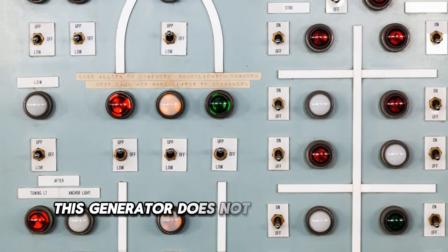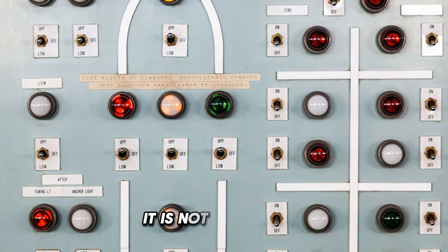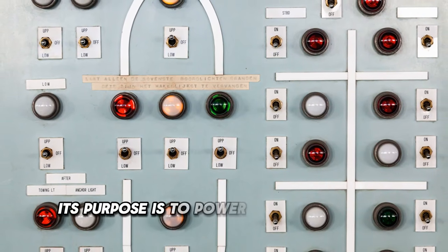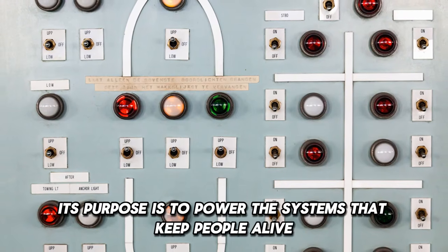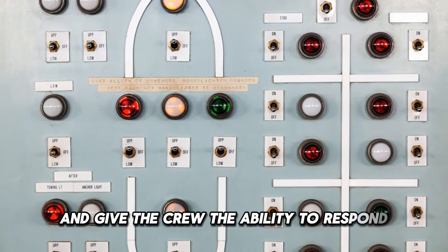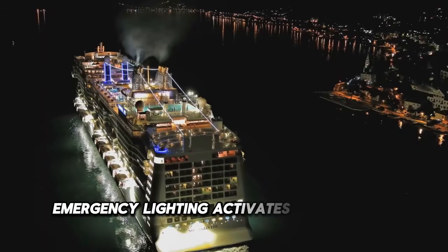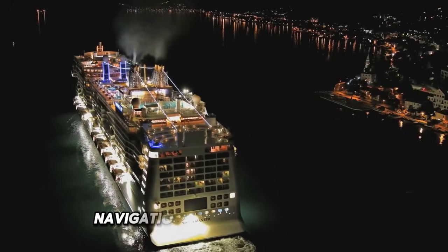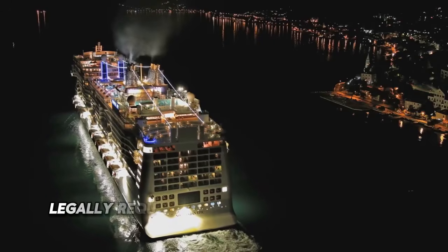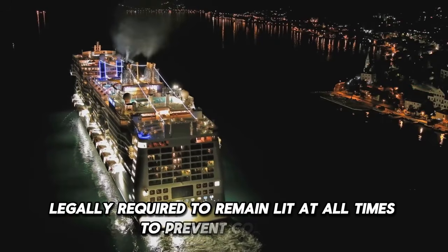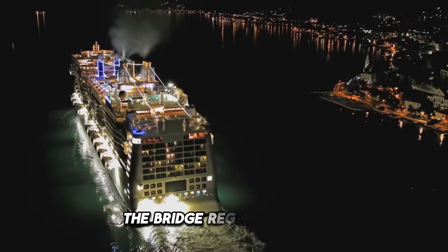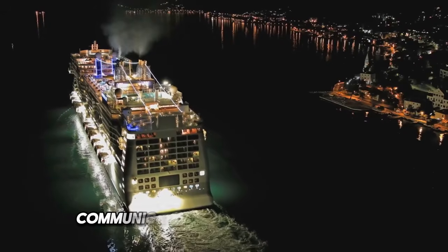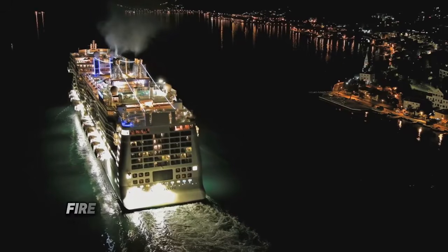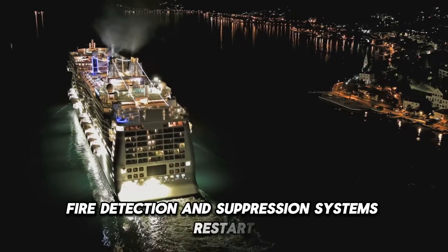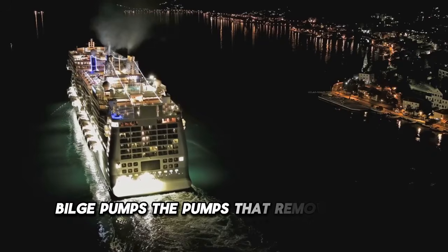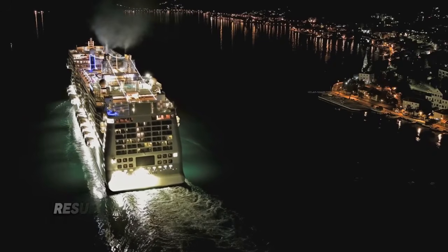This generator does not restore full ship power. It is not designed to. Its purpose is to power the systems that keep people alive and give the crew the ability to respond. Emergency lighting activates throughout the ship. Navigation lights come back on, legally required to remain lit at all times to prevent collision. The bridge regains power. Communication systems come online. Fire detection and suppression systems restart. Bilge pumps, the pumps that remove water from the lower hull, resume operation.